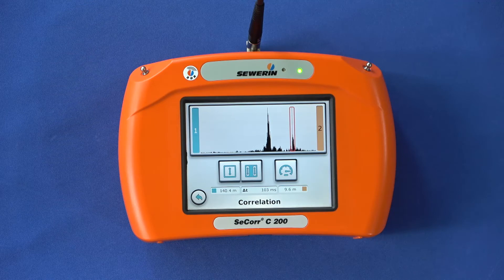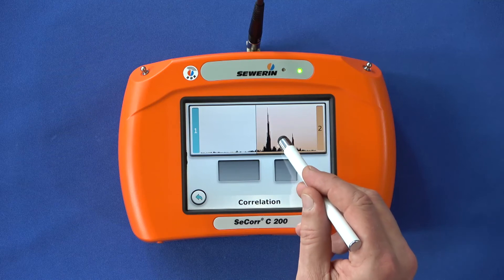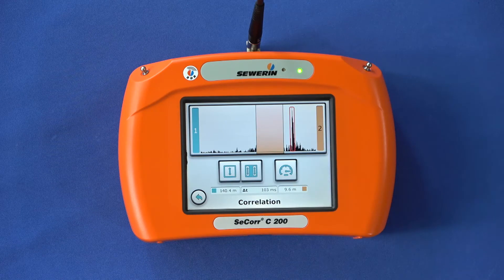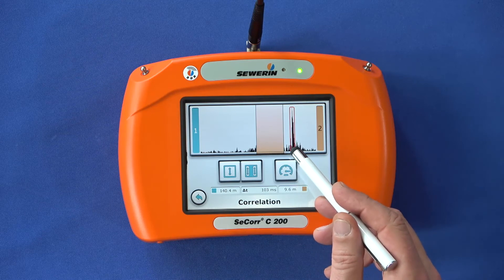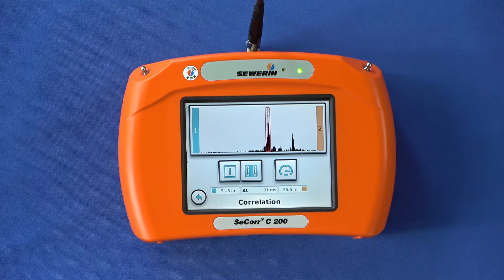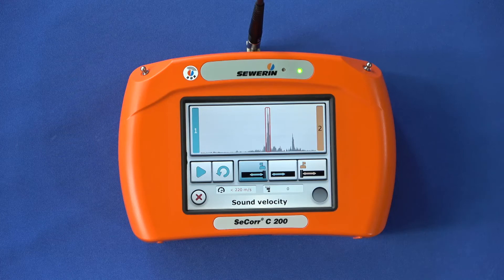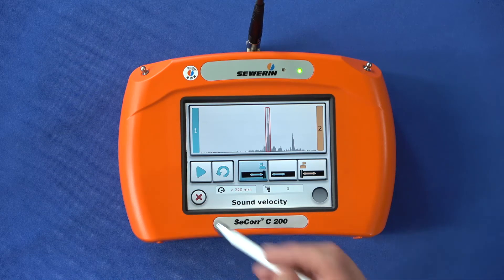For better visibility of a second peak you can suppress the peak corresponding with a known position. To do this, tap two positions in the graphic to the left and right of the peak to be hidden. The hidden area is filled in orange and the curve is recalculated. The formerly smaller secondary peak can now be seen much more clearly. You can undo your selection by tapping the show peak button. Start the feature of a sound velocity measurement with the corresponding button. A second measurement on the pipe section but with an artificial leak can completely rule out the influence of the speed of sound. We recommend the Sewerin seminars for further information on this topic.